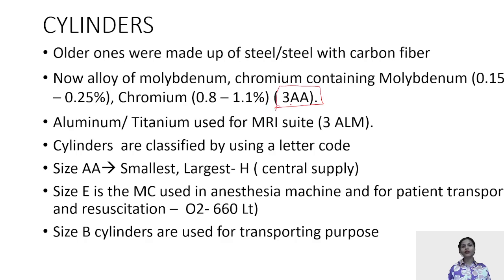This is the marking which is present on the cylinders. It is made up of molybdenum plus chromium. But there are certain special cylinders also which are MRI compatible. Those cylinders are made up of aluminium and they are marked by 3ALM. That stands for aluminium. These are special cylinders meant for MRI use.